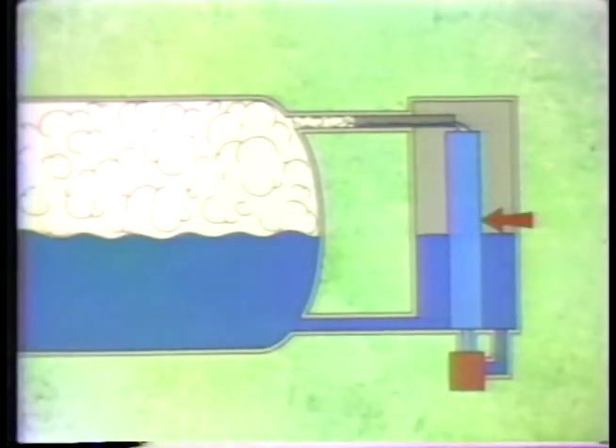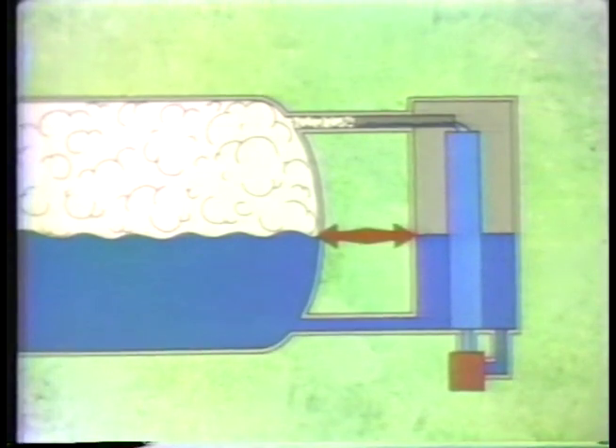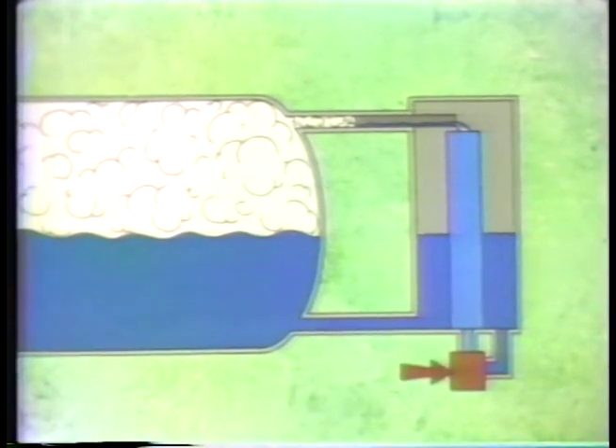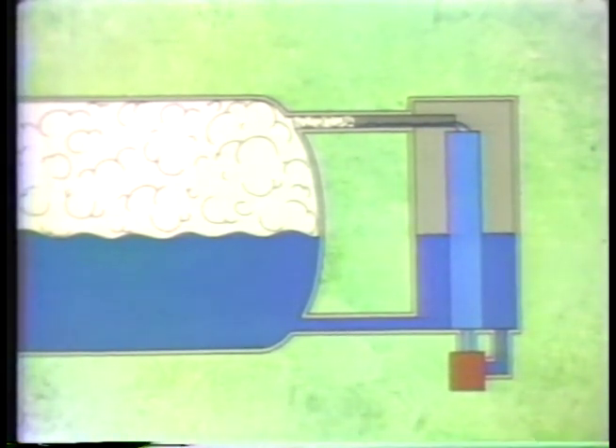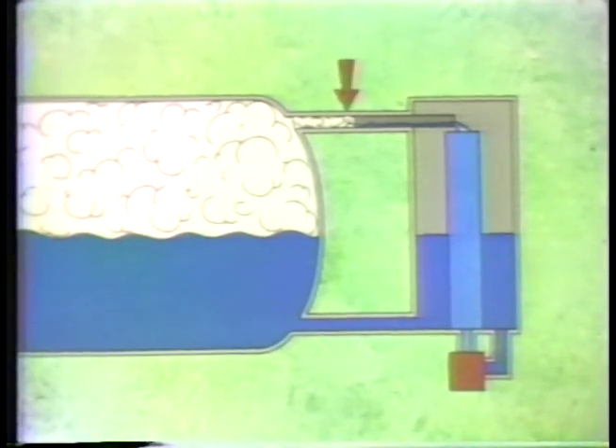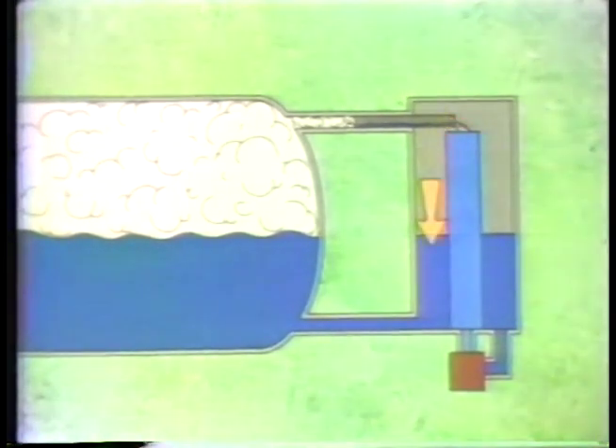The inner column is the reference leg and, as before, is kept filled with water. The reference leg is surrounded by the variable leg, whose water level is the same as the level in the boiler drum. The two legs are connected to a differential pressure measuring instrument. Both legs are connected to the boiler drum so that the effects of boiler steam pressure are eliminated. The reference leg is kept full by condensation of steam in the upper tap — condensate drips into the reference leg, and excess simply overflows into the variable leg and eventually returns to the boiler drum.